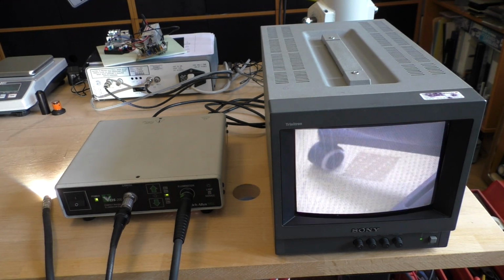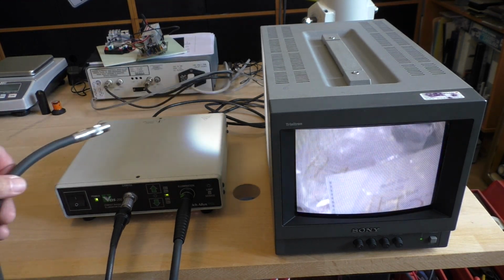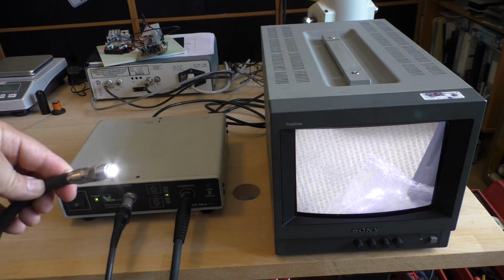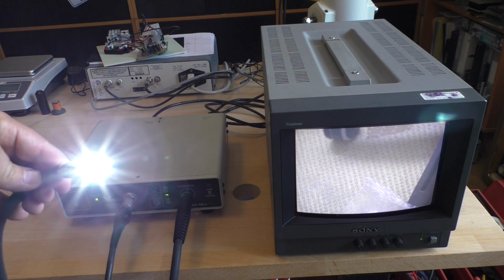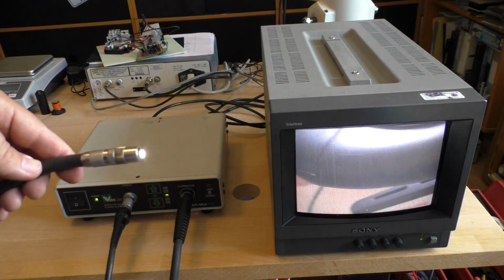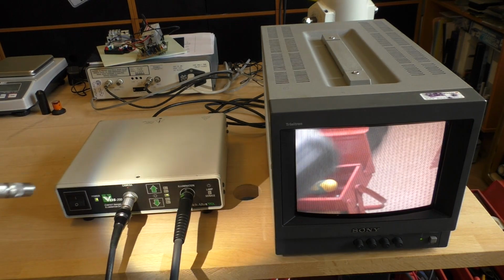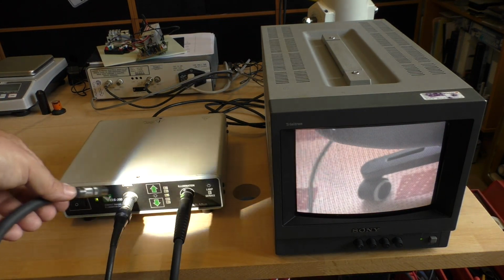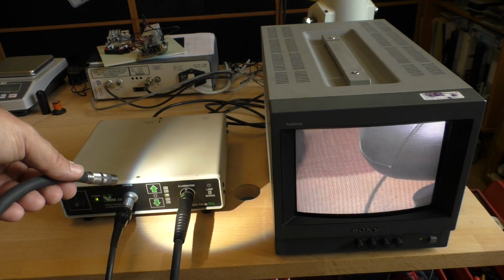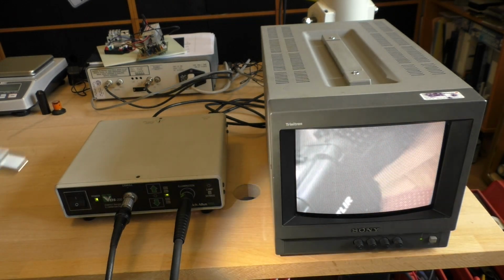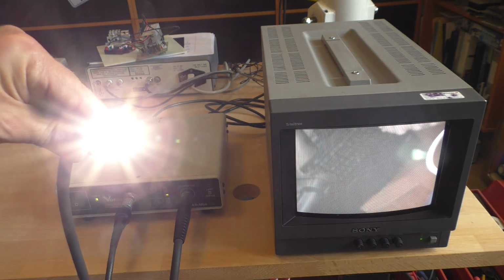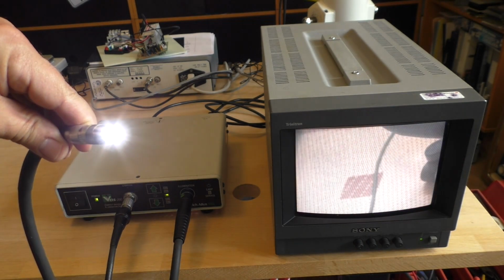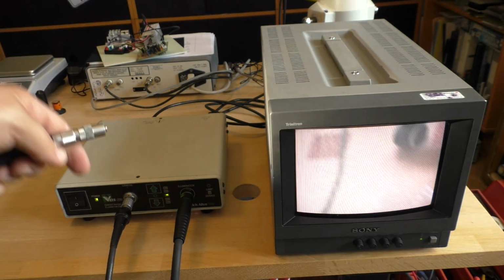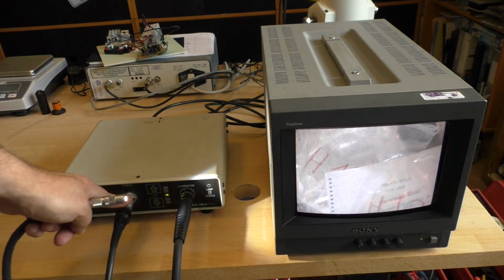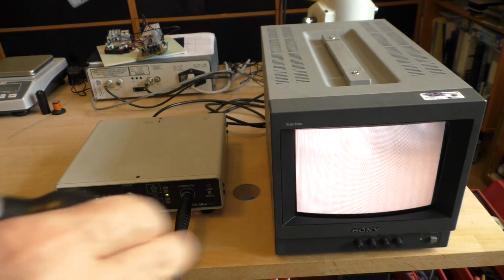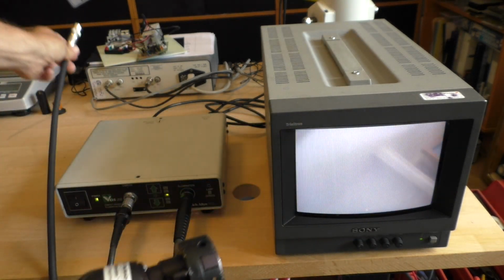And that's how it looks when the system is working. Here you have a glass fiber optical light guide, so that's the word. Inside the box here is a xenon light bulb, a pretty small xenon discharge bulb. It makes a pretty bright light, which is important to see anything through those endoscopes. So that plugs in here. That's the connector from the camera, which is this here.